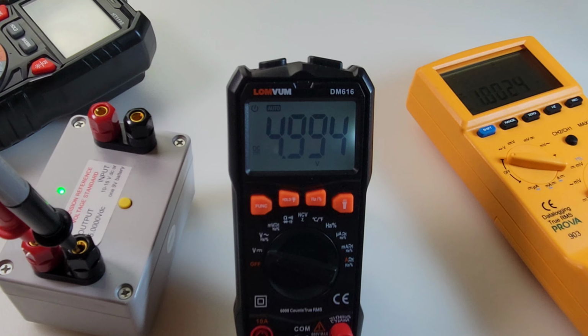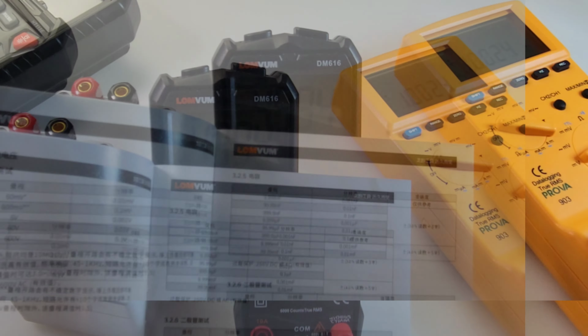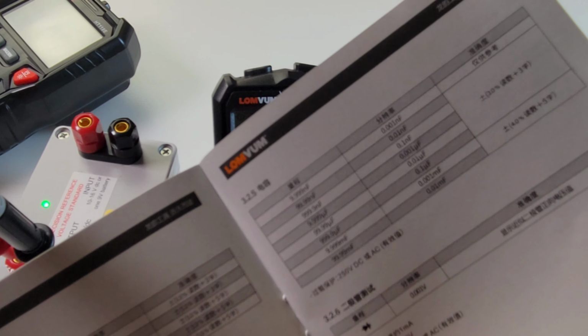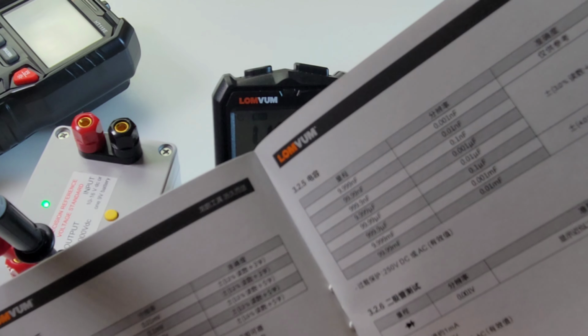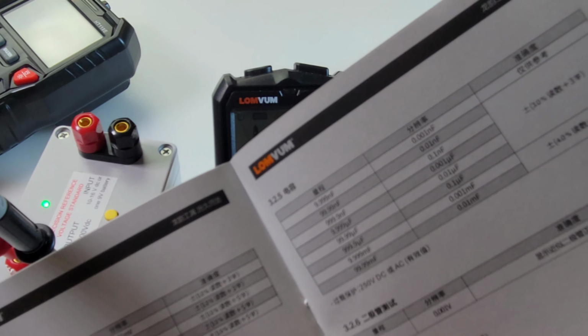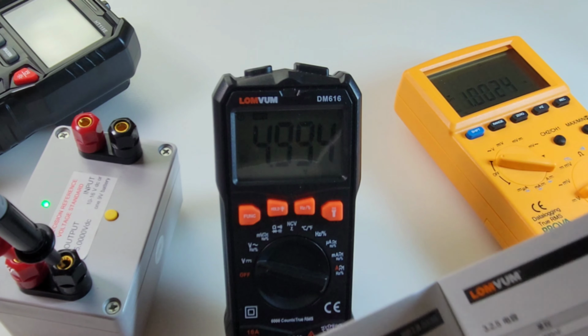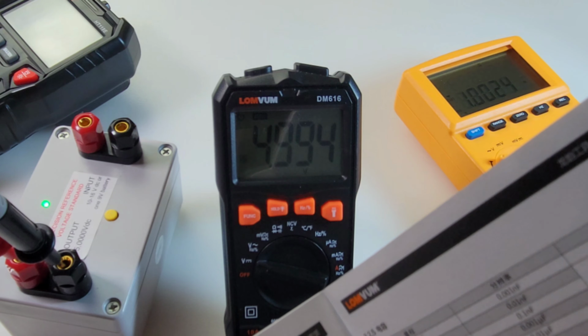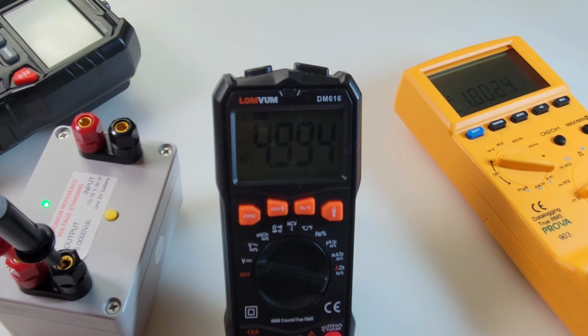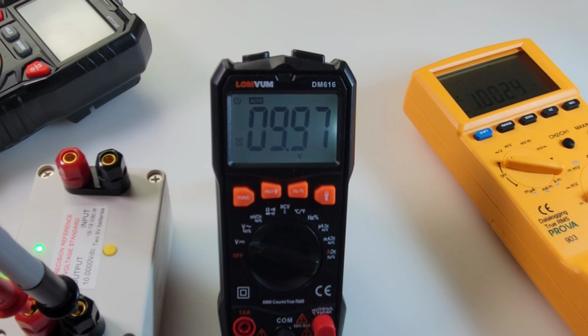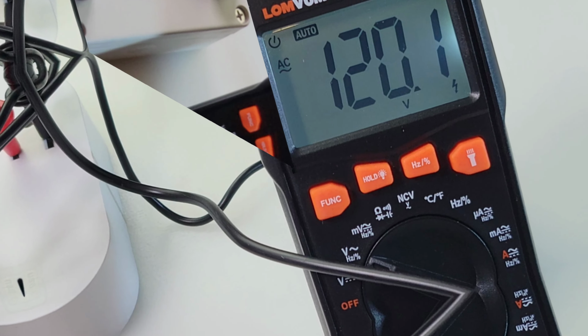5.000 is what we want. 4.994 is what we get, 6 counts off. Now, interestingly enough, in DC volts, we should have an accuracy of 1.2% plus or minus 3 digits. So, you know what? We are slightly out of spec. And with a 10 volt reference coming in at 9.97 volts.